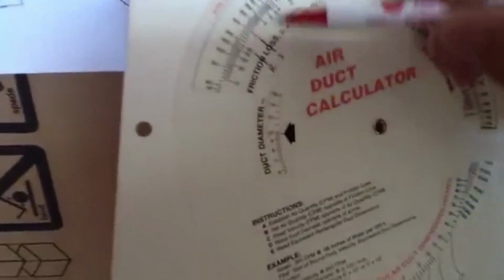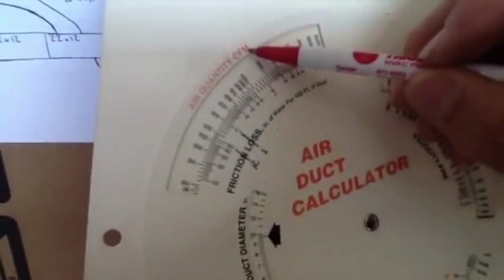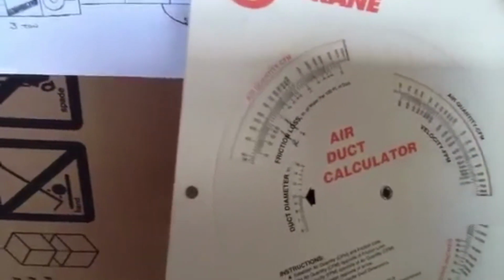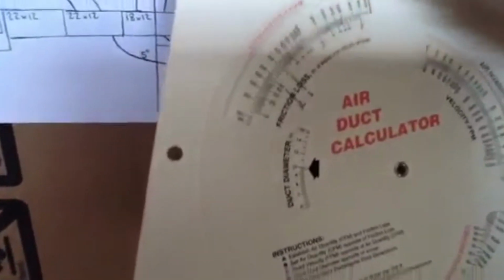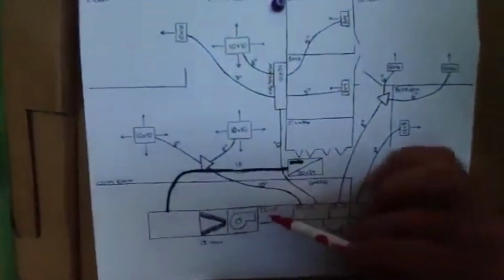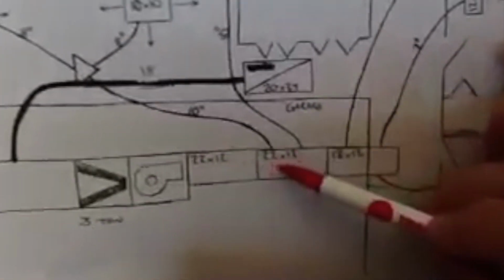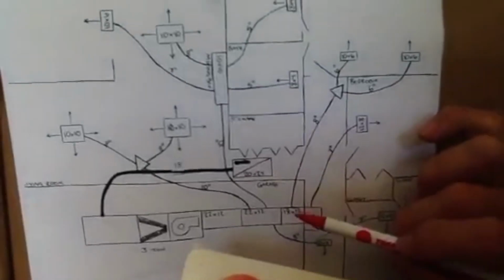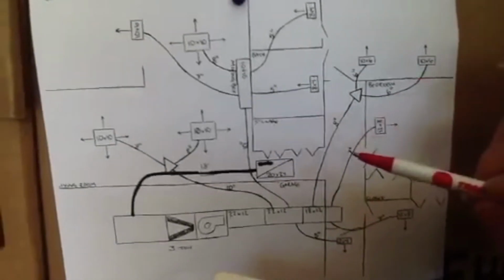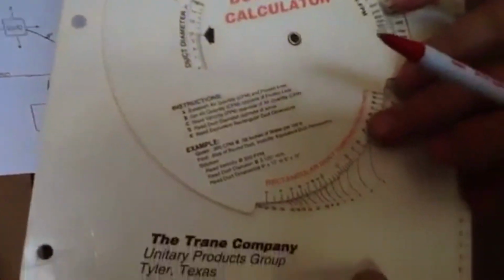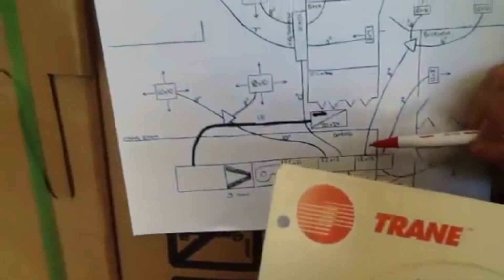So let's just talk about this second. We have duct diameters, and we have air quantity in CFMs. The industry standard is 400 CFMs per ton of supply, okay? So now let's talk about this. Right here, we're going to talk about a 3-ton system. We basically came off this particular air handler and we designed this trunk line here based on the 3-ton rectangular duct system, which down here at the bottom is where this line is, okay? But we're not going to get into that today. We're going to talk about this.